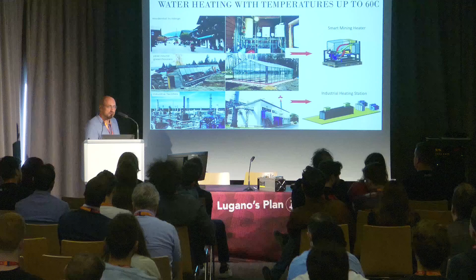And here we have fantastic use cases, because compared to water blocks, whose cooling efficiency is low, we have to keep the coolant or water temperature at pretty low numbers, like 35 or 40 degrees, which isn't enough for most heat consumers. Here, with a heat exchanger, we can raise the water temperature up to 60, even 65 degrees — this is what we tested. This opens up a huge market for utilizing that heat. We can provide it to greenhouses, private homes, chemical industry, whatever. We can replace old heating stations within a city that are still burning gas or diesel with industrial heating stations and just provide heat for free. Of course, we'd want a discount on electricity, but that's something to agree on with the government. It's a win-win situation for everybody.